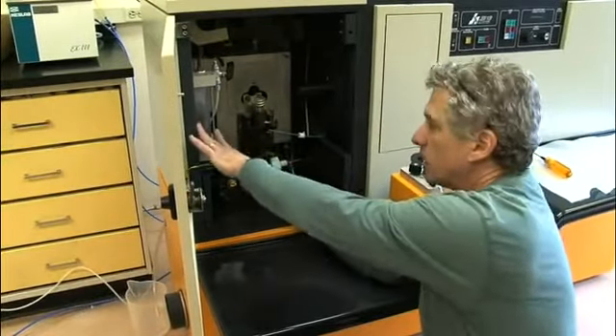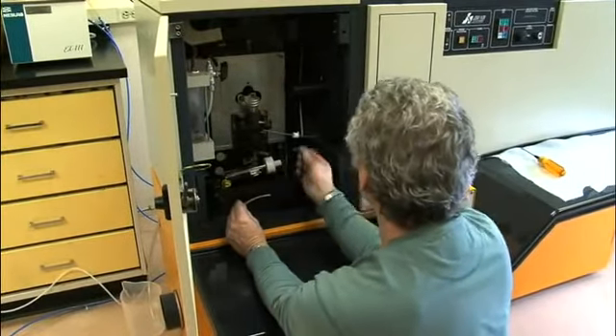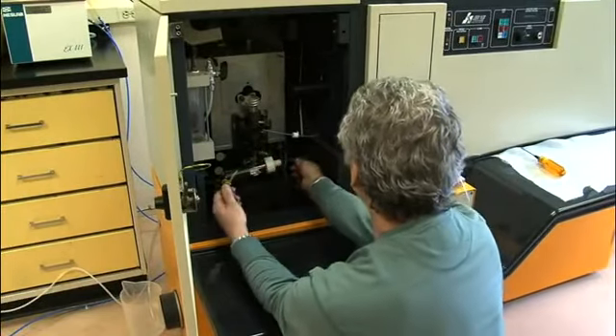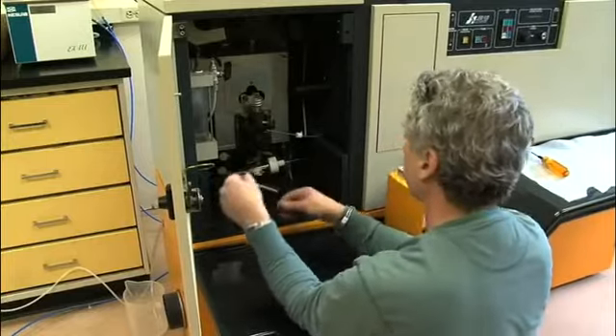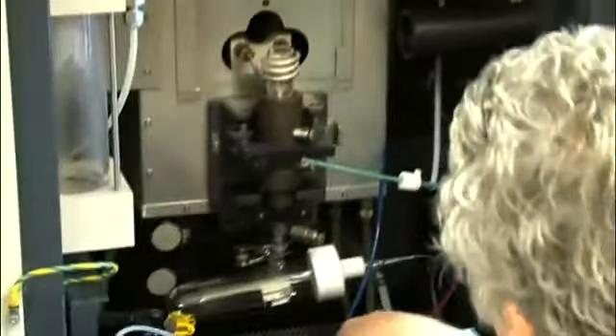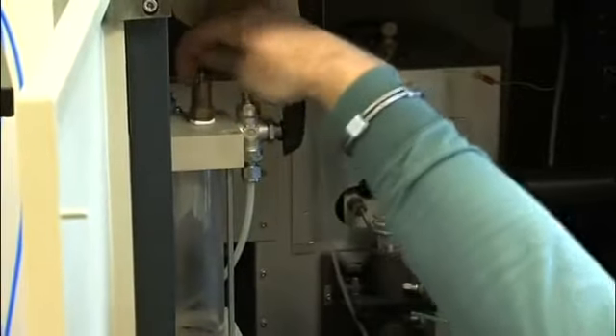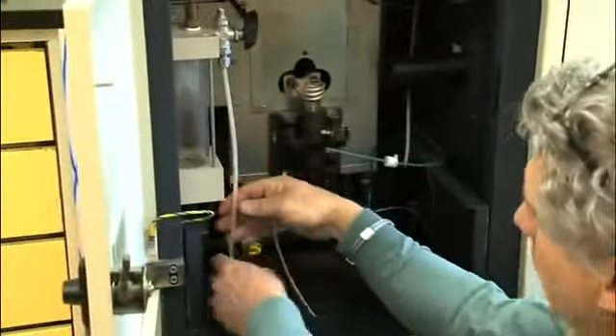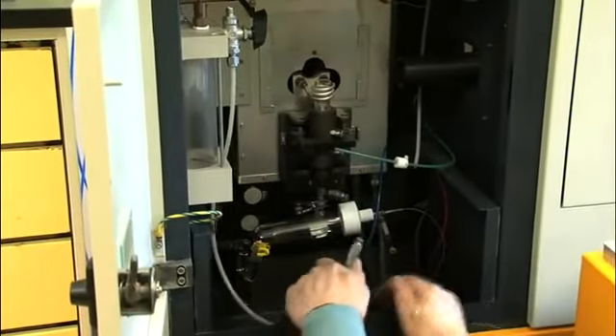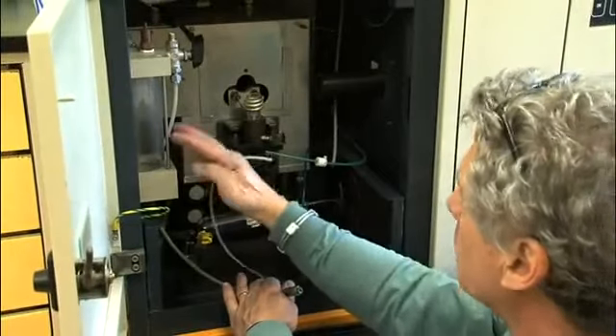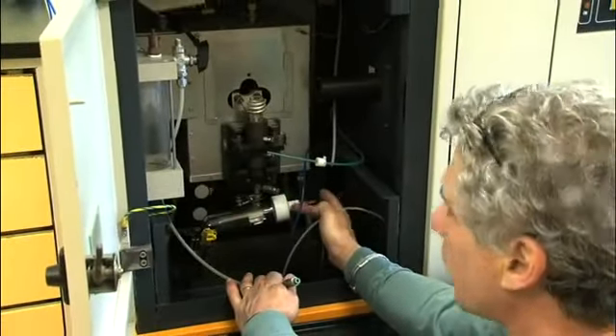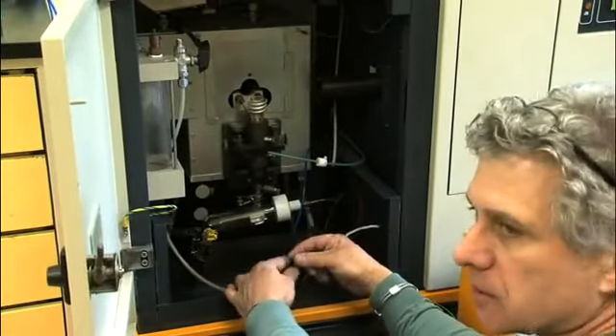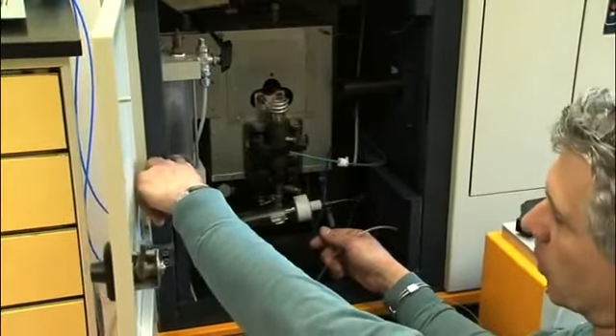If you're going to run any samples with high salt, you want to use the humidifier because it'll clog up this type of nebulizer. It's the glass concentric. It'll clog up the tip with salt if your sample is high salt. So what you do is take this hose off and feed it into the top of the humidifier. If it reaches over, it should reach over there. Anyway, it goes in this fitting here, and then this is your output. Your output will plug back into the neb. So you're humidifying the nebulizer gas so that it prevents clogging of salt on the tip. Once it clogs, it's shot. Put about this much DI water only in this. If you're not running any high salt, you don't need to worry about that.